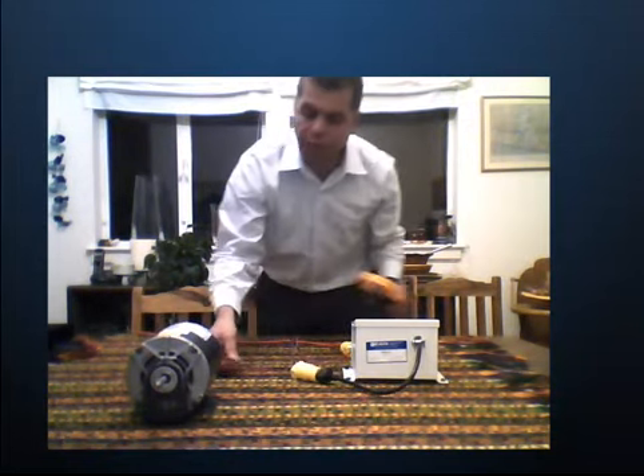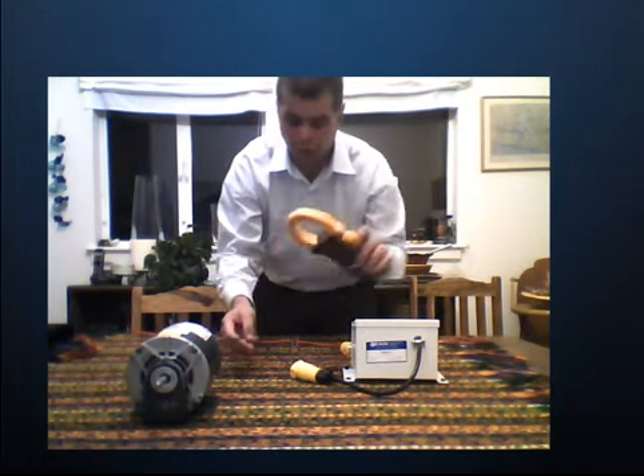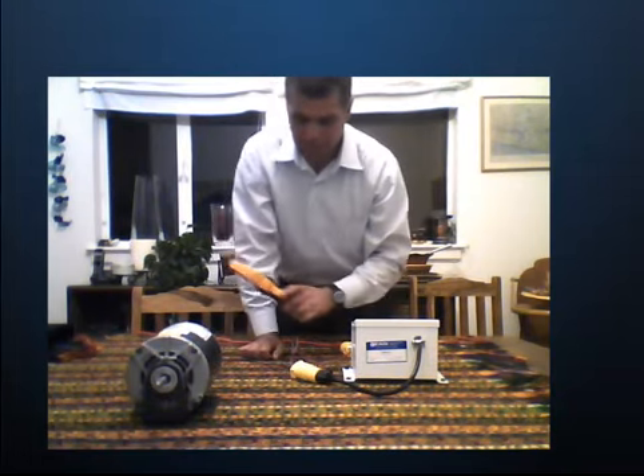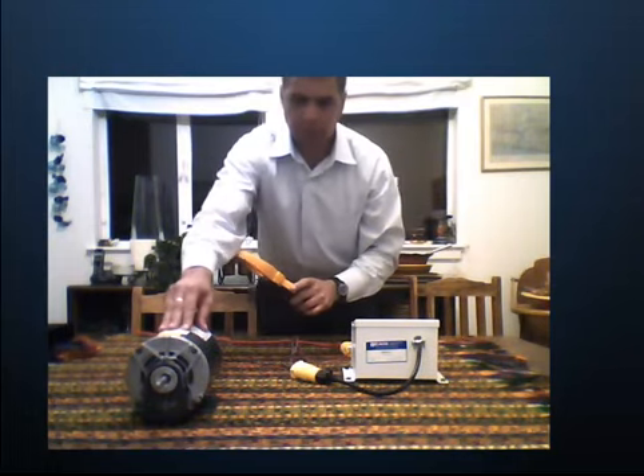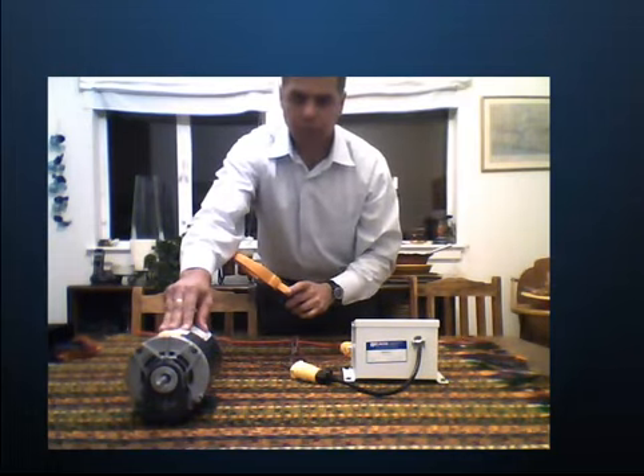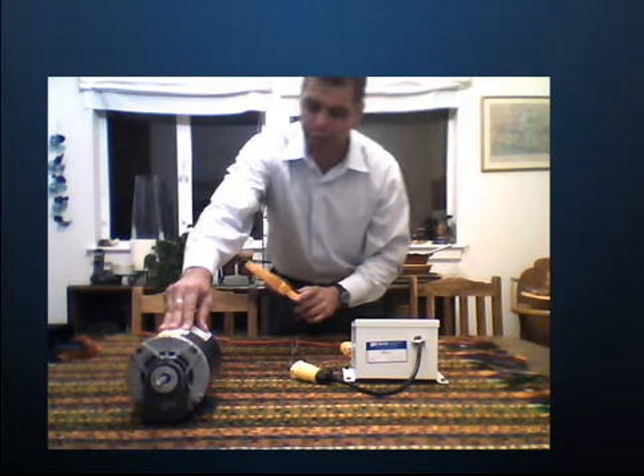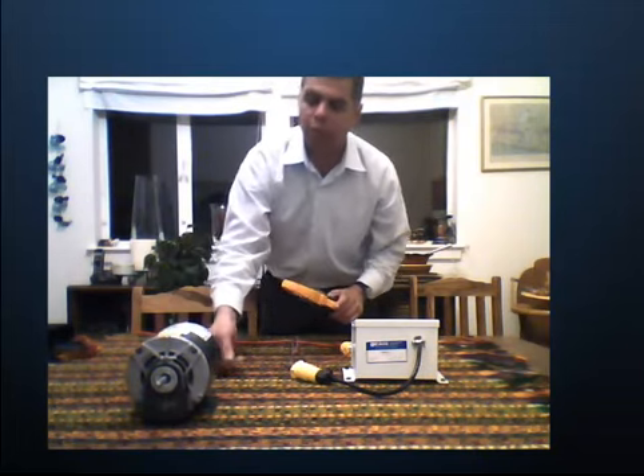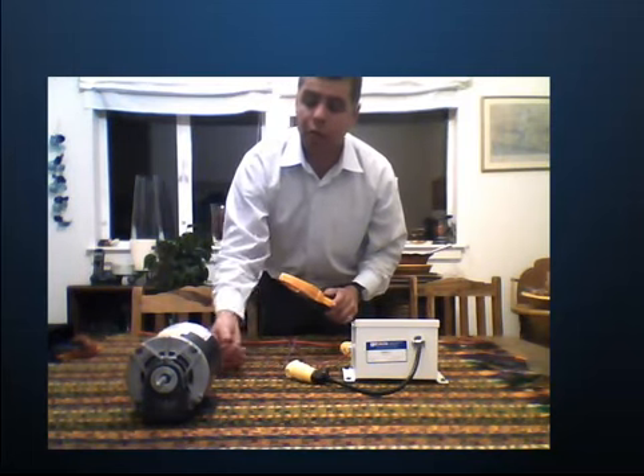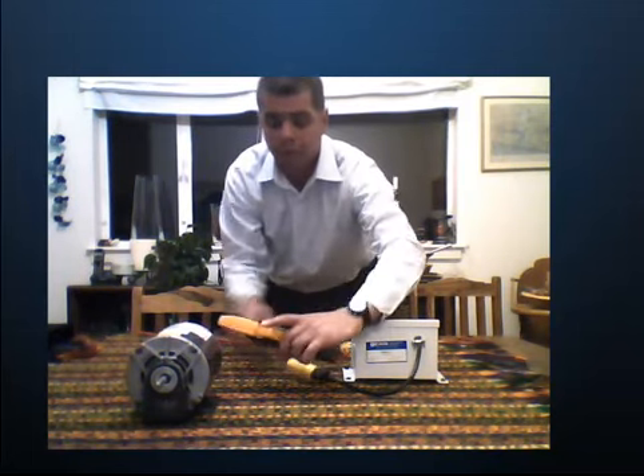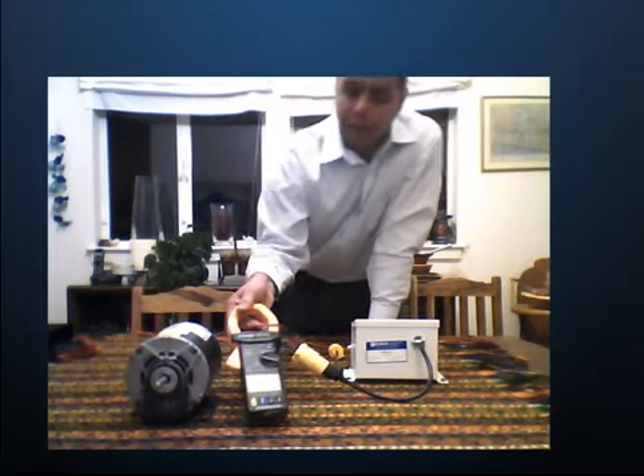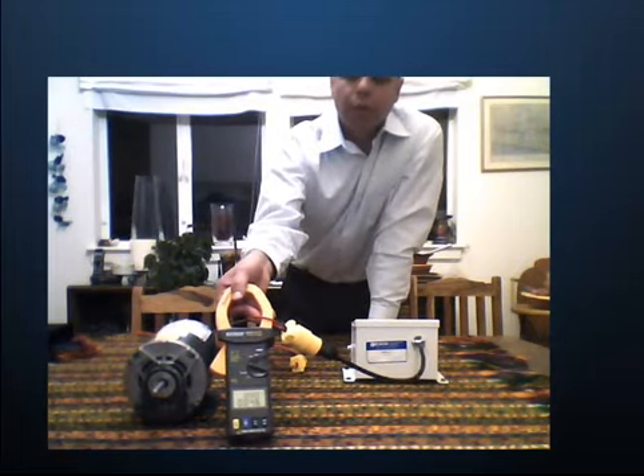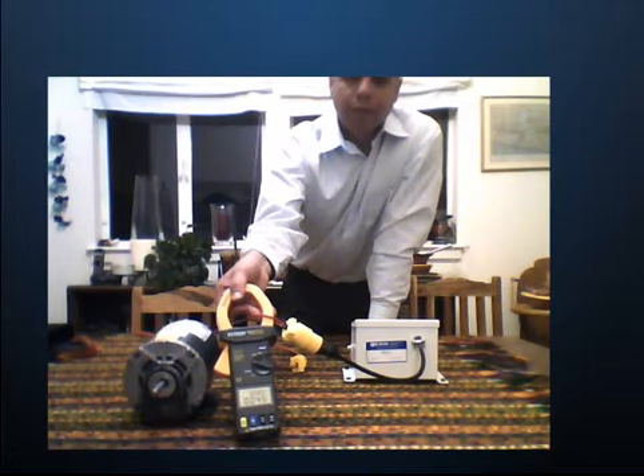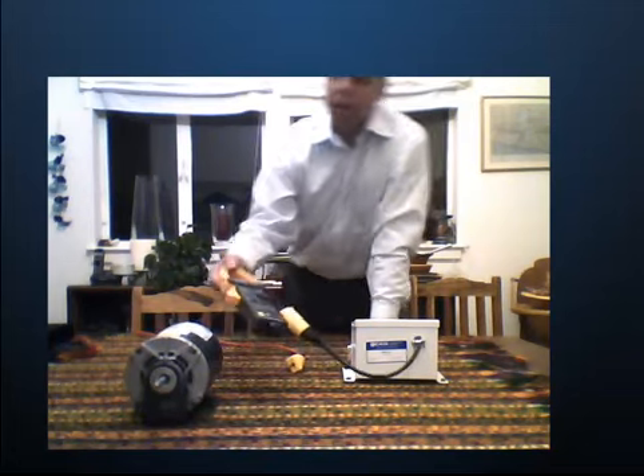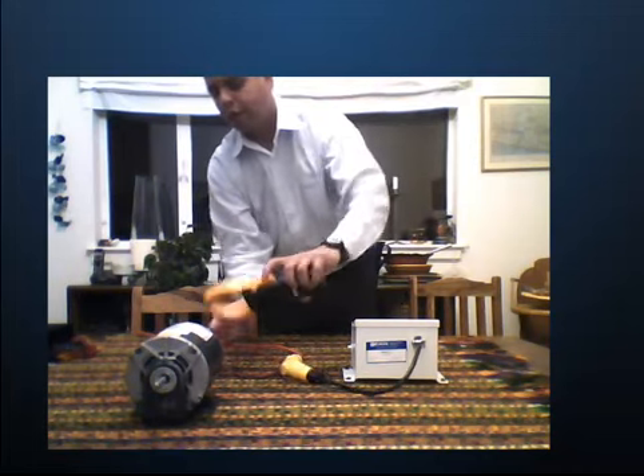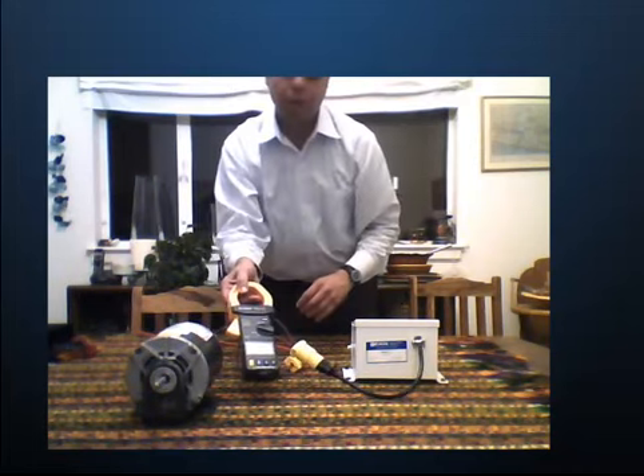And I'm going to take a reading now towards the load. So even with this product, it doesn't cause the motor to work less, or take away from its effectiveness, right? Correct, nothing changes in that motor operation. That is absolutely correct. Now I'm going to take a reading, and what I'm going to see is that the motor still draws 4.5 amps at 60 hertz. You can see it. Yes, it's the same thing on the other side, in the opposite direction.